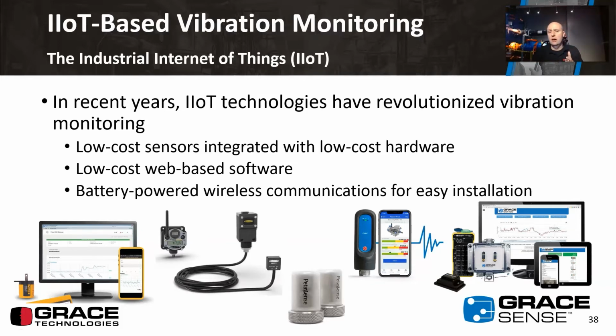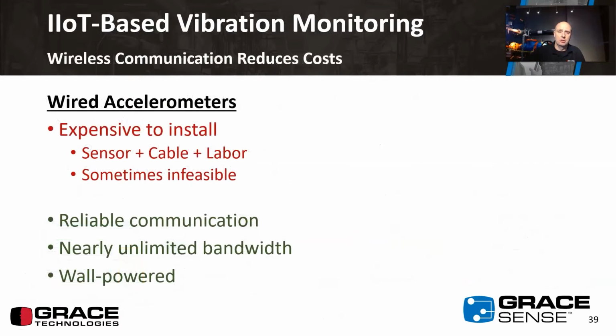These are low cost, usually MEMS or piezoelectric based accelerometers integrated with a wireless component, allowing low cost hardware coupled with low cost web-based software to deliver vibration information readily to a user via the cloud. They're typically battery powered, self-contained, and can usually be magnetically deployed on a motor or bearing just by plugging the battery in and placing it down - a lot easier than the status quo of a full installation with conduit and so on.